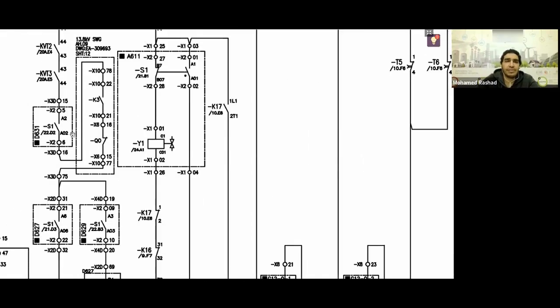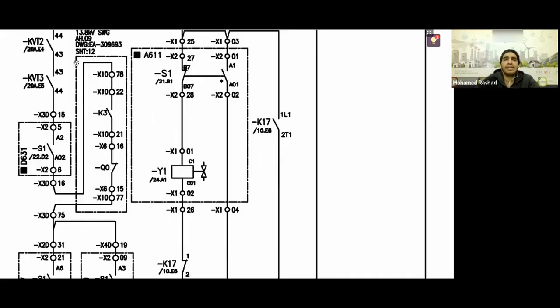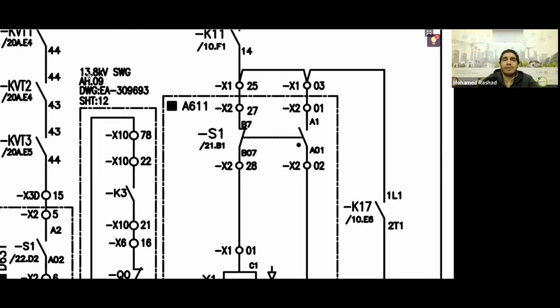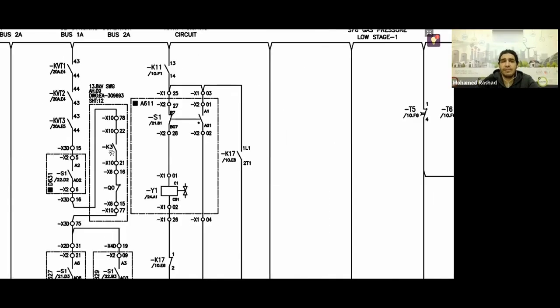Here, this condition is presented to you as you see a box made. Also, what is written here is that it is coming to you from a 13.8 kV switchgear, and it provides you with the drawing number and the sheet number. If you go there, you will discover what these two are. I am telling you this because I like to study this when we study the other. The breaker Q0 is racked in but open, meaning it is ready to be closed or ready to be in service but not closed. It must be open. So I made sure it was open.